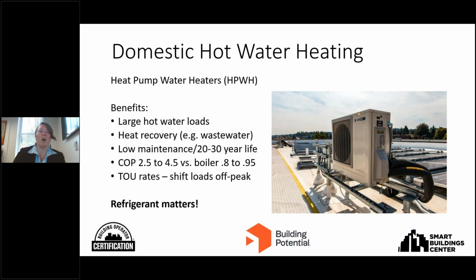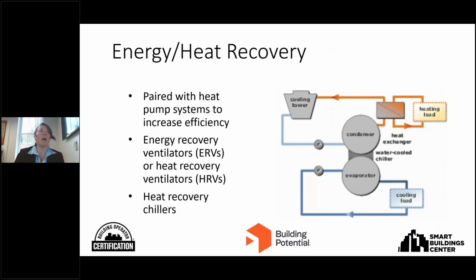Domestic hot water heating. I also mentioned energy and heat recovery, pairing with heat pump systems to increase efficiency dramatically. This works really well where you have simultaneous heating and cooling loads. For example, water-cooled chillers can recover heat that would normally be rejected by cooling towers, and that heat is transferred to needed loads, significantly reducing energy costs. That's what this diagram shows, a version using a heat exchanger to recover that heat.